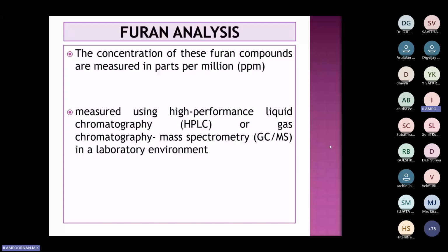In the oil, there is a reflection of furans, which are one of the important compounds. You take the oil and put it in an HPLC, that is High Performance Liquid Chromatography, and pass the oil through it. It separates the different furan contents and shows the ppm level, parts per million. So it's not possible to open the transformer and take the paper directly, but I can test the oil, which gives an indirect indication of what's happening in the paper.